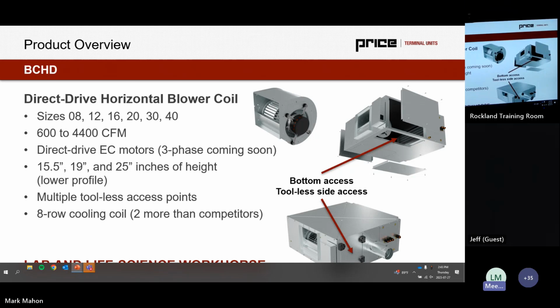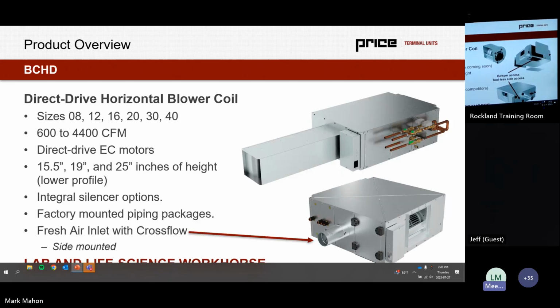It's like an indoor air handler built for lab and life science type work. You know, solid metal liner options. Once again, fresh air inlets, in this case on the side downstream of the cooling coil, which maximizes the log mean temperature difference of that coil. It essentially keeps the difference of air temperature and water temperature as large as possible, which is going to allow for more total capacity. Silencer options and factory mounted piping packages on this as well.